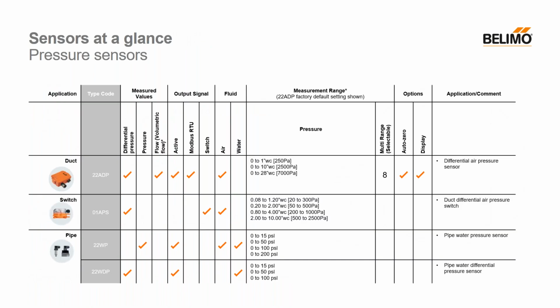So a quick overview of our pressure and DP sensors. Again, we have the active air side differential pressure sensor, which is available with Modbus communications and an LCD, as well as auto zero calibration. The standard air pressure switch is simply an airside DP switch used in safety applications and things like that. And then water pressure and water differential pressure with varying different pressure ranges and analog outputs. So the water side pressure offering is fairly basic, while the duct air side differential pressure offering is pretty sophisticated, and that air side pressure switch is just what it is. It's an air side pressure switch.